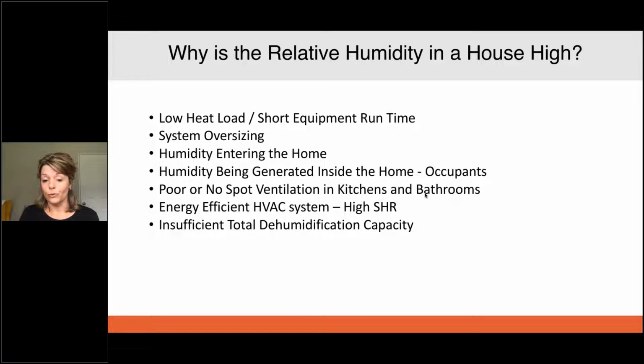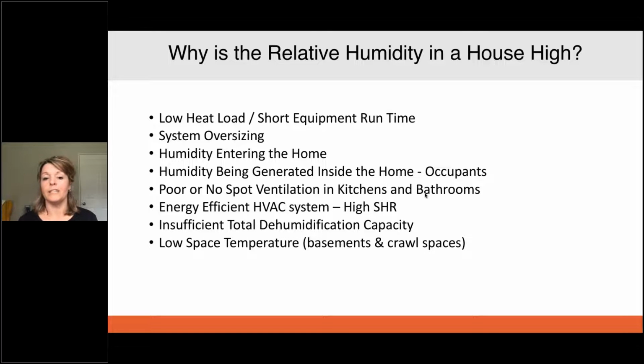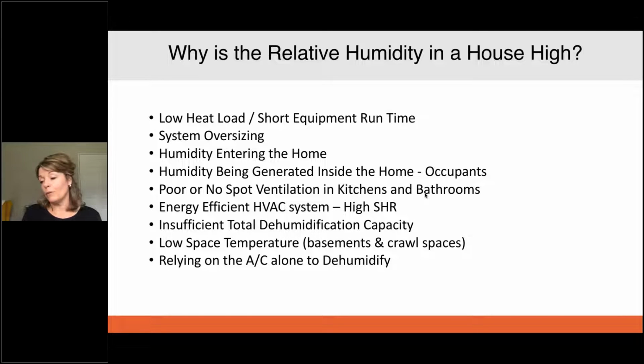We're not getting enough total dehumidification because of that, and low space temperatures. So in basements and crawl spaces, typically we don't need a lot of air conditioning. You actually put colder air into those spaces and automatically increase the relative humidity. That's when we can't rely on our AC system alone to dehumidify.